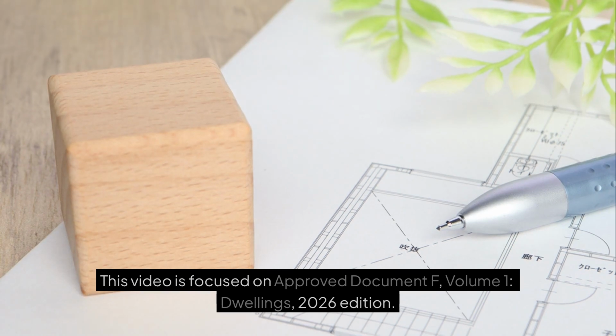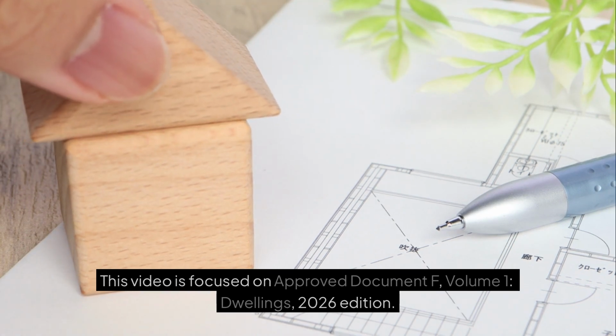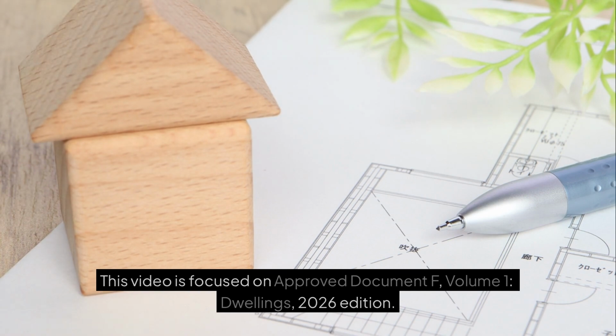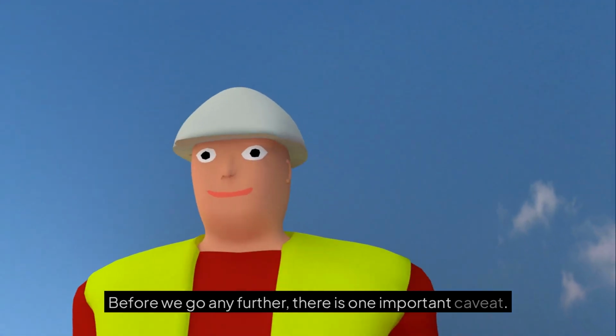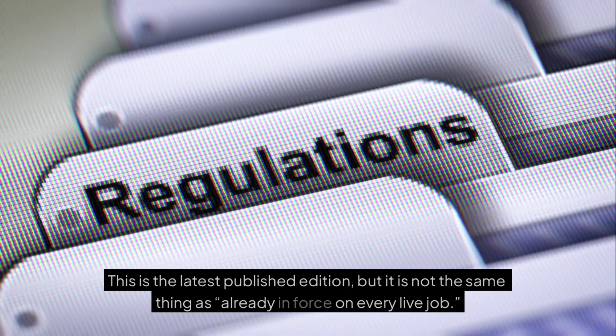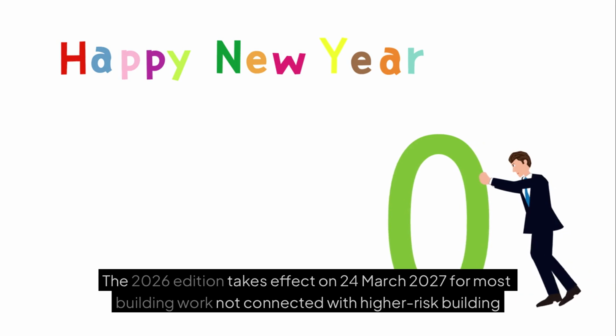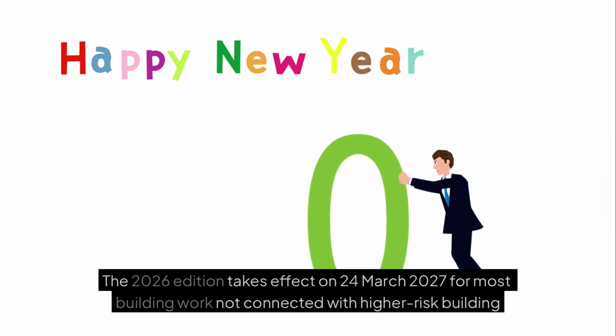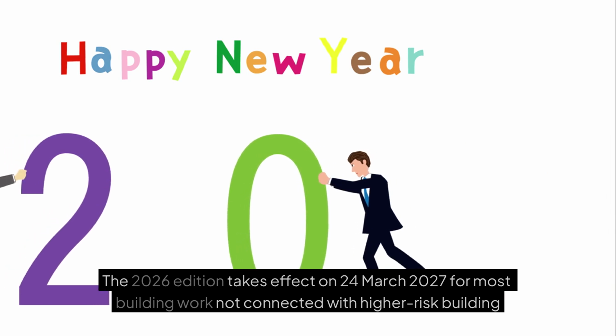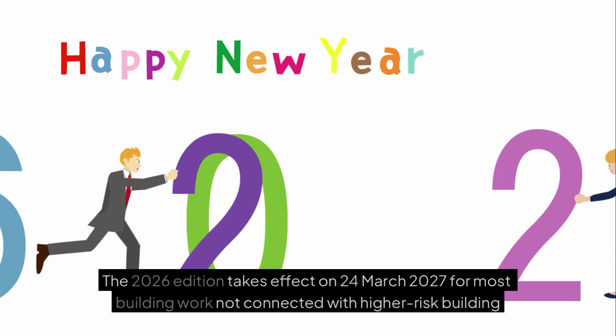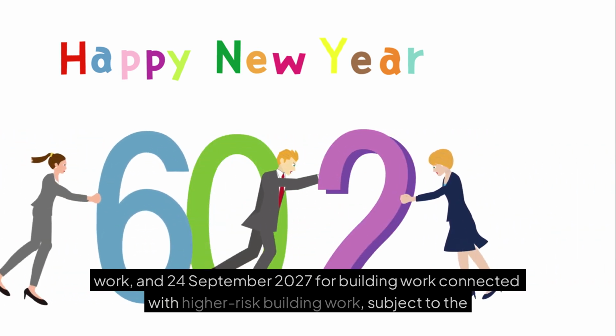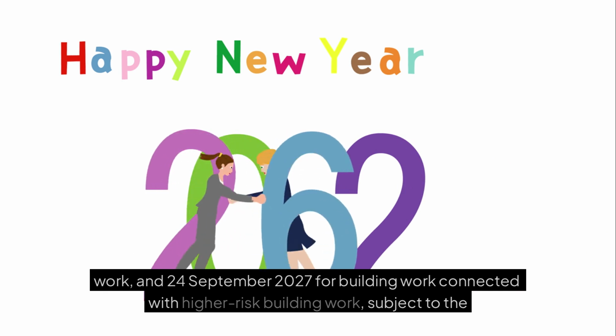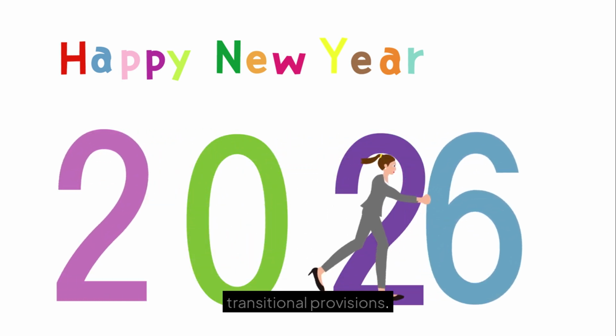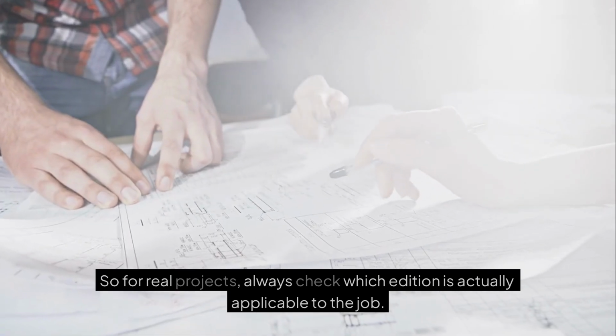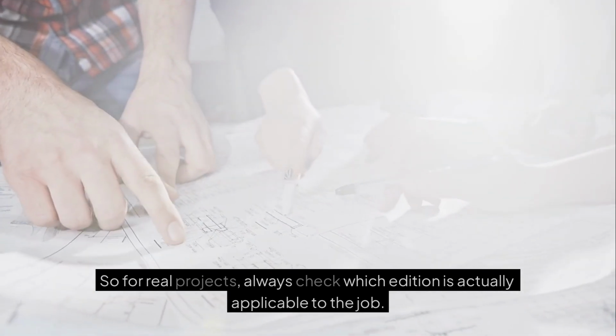This video is focused on Approved Document F, Volume 1, Dwellings, 2026 edition. Before we go any further, there is one important caveat. This is the latest published edition, but it is not the same thing as already in force on every live job. The 2026 edition takes effect on 24th March 2027 for most building work not connected with higher risk building work, and 24th September 2027 for building work connected with higher risk building work, subject to the transitional provisions. So for real projects, always check which edition is actually applicable to the job.